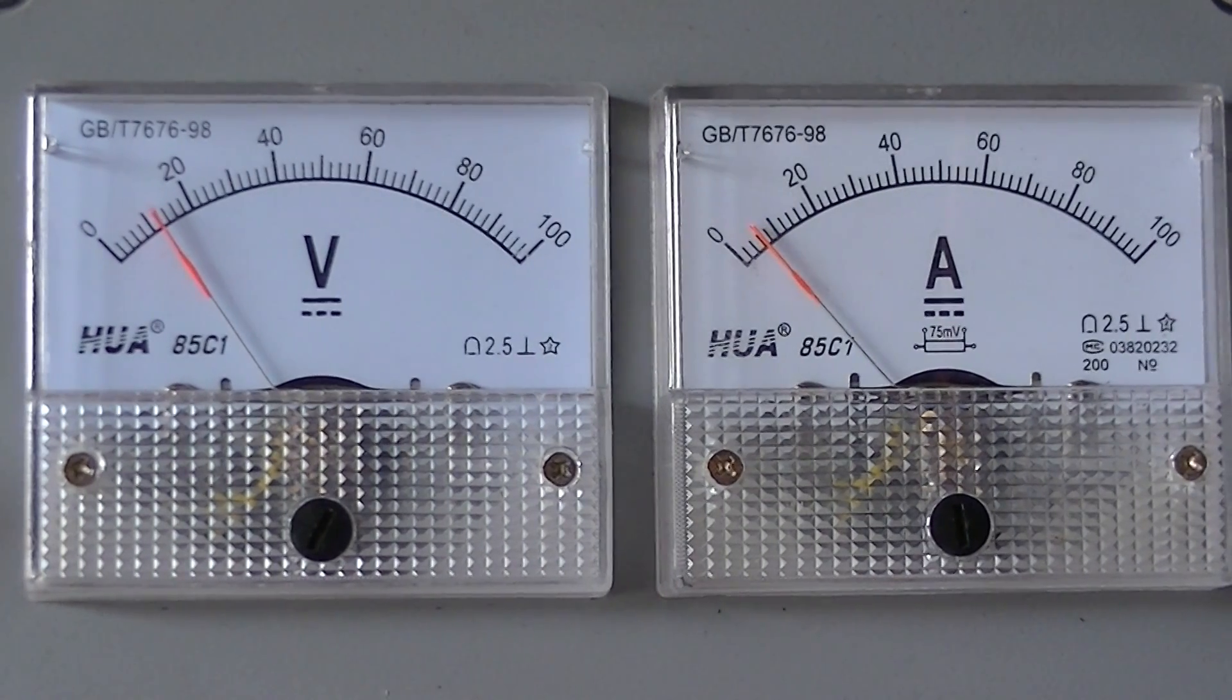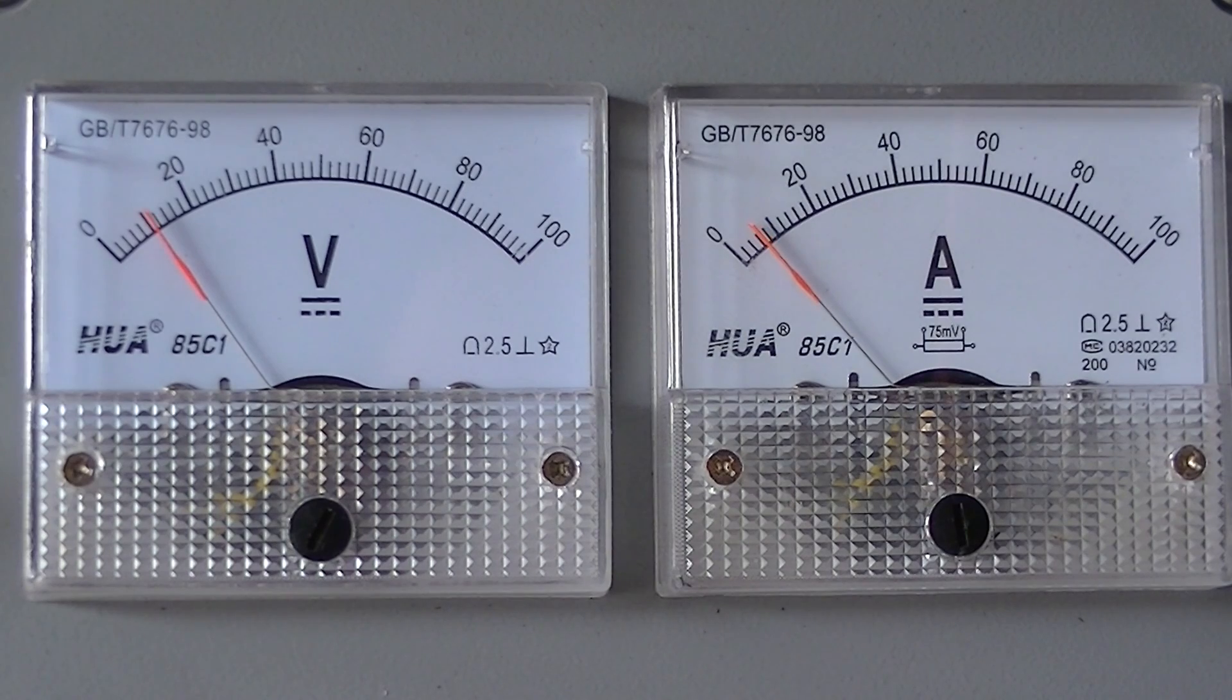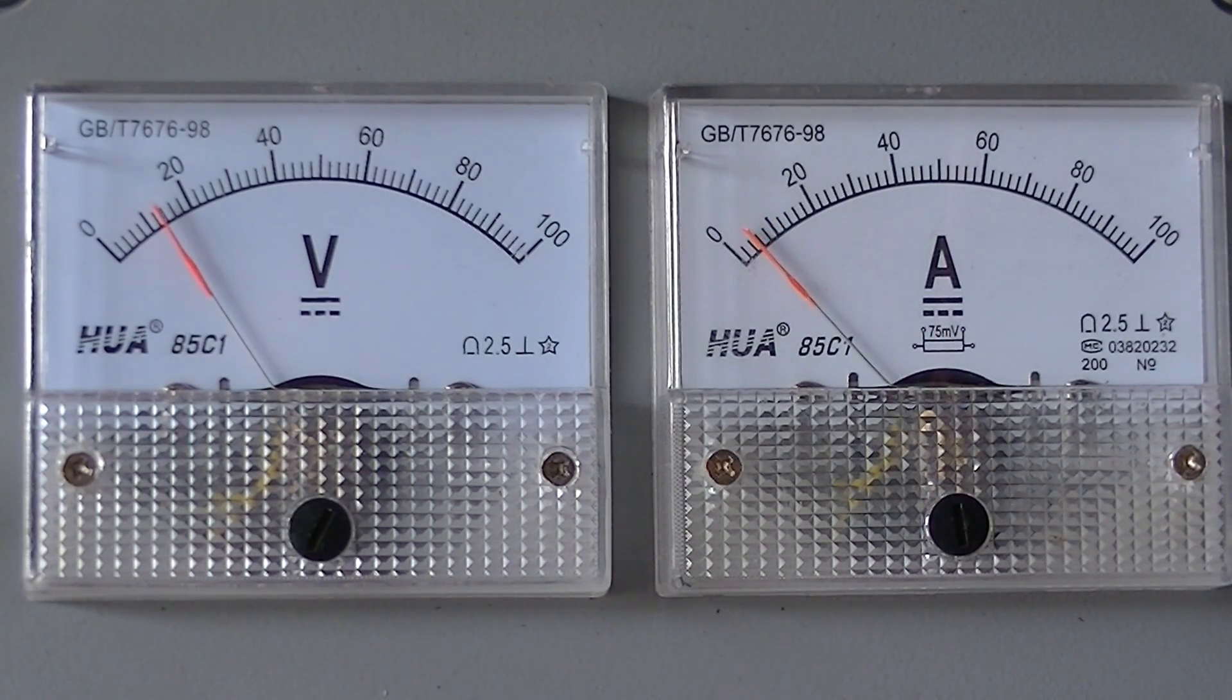You want to see what the winds are doing? Remember, amps times volts, that'll give you watts. You always want to do the DC watts from right here. I'm within a foot of the rectifier, so this is pretty damn good readings. There's really no DC voltage drop because I'm using number four wire and I'm right here.